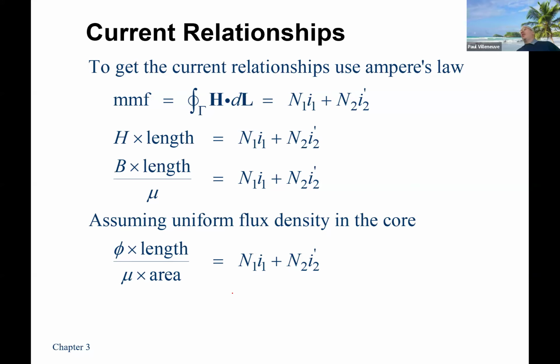The other thing too is that you actually use bigger wires or bigger copper conductors on the secondary side, the low voltage winding, than on the high voltage winding because you get more current flow. So you don't run the same size conductor, you run smaller because everything is trying to be built cheaper, right? If I can get something that's going to have 1/3 the current, I'm not going to run the same wires because it's going to be a lot cheaper for me to run smaller wires on that higher voltage winding.